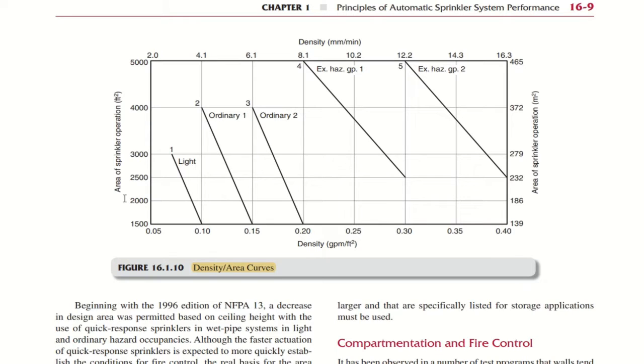Here on the left-hand side, on the y-axis, you have the area of sprinkler operation in square feet, and in square meters as well. On the x-axis you have density in GPM per square foot or density in mm per minute. We have various kinds of hazard occupancies that we will discuss in later chapters. However, here we will just go through these occupancies. For light hazard occupancies, we have the density as 0.1 GPM per square foot at 1500 square feet area. For ordinary hazard occupancy, the minimum requirement is 0.15 GPM per square foot at 1500 square feet area. For ordinary hazard group 2 also, 0.2 GPM per square foot at 1500 square feet area of sprinkler operation.